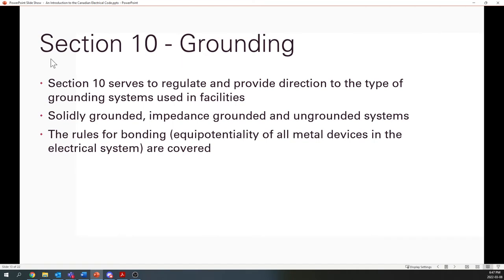Section 10 is grounding. So as we all know, grounding is connecting something to the earth. And that is the definition that code uses, connecting electrical equipment to an earth reference that should be theoretically 0 volts. That is a reference that, if it was hit by lightning, for example, you could drain off that current, that voltage, to ground.